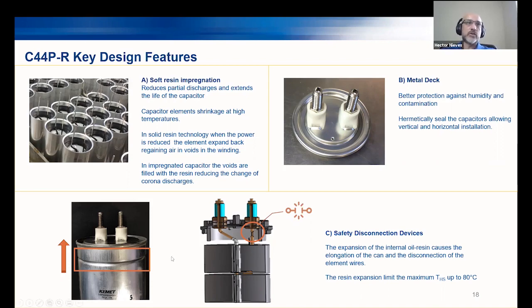And of course, the disconnection device. There are different ways to do a disconnection device. Some designers, and we also have that technology, disconnect the device from the deck, so the deck will do the disconnection. In this case, the canister is the one that makes the disconnection. When this capacitor starts overheating, the resin starts expanding, and you can see this notch here on the surface of the canister. It starts expanding inside, and it will disconnect a cable, the connection of the cable inside of the capacitor. So that will allow the capacitor to avoid potential explosion.